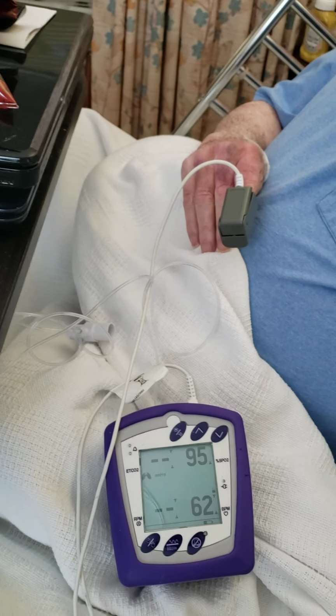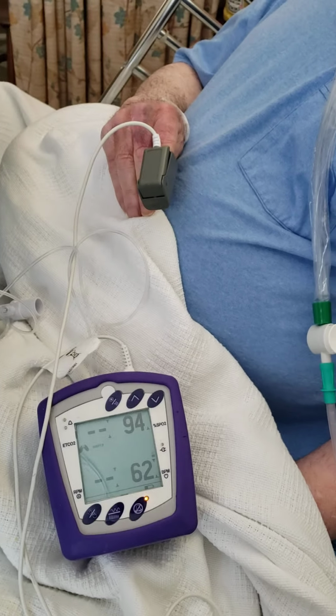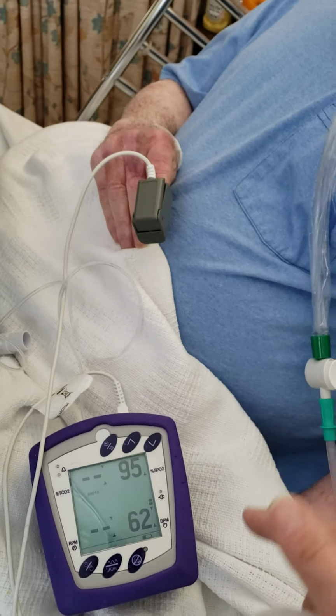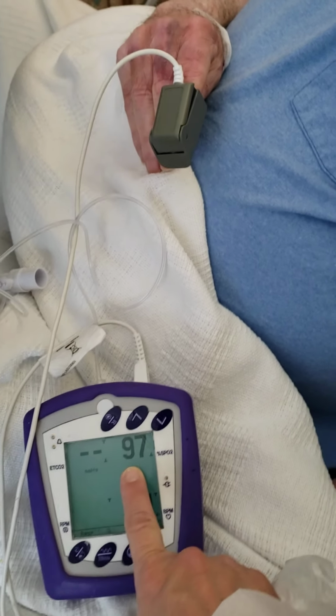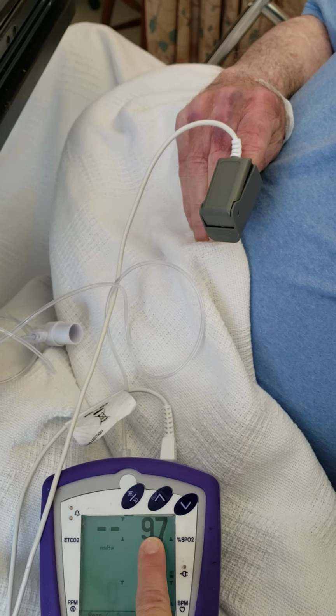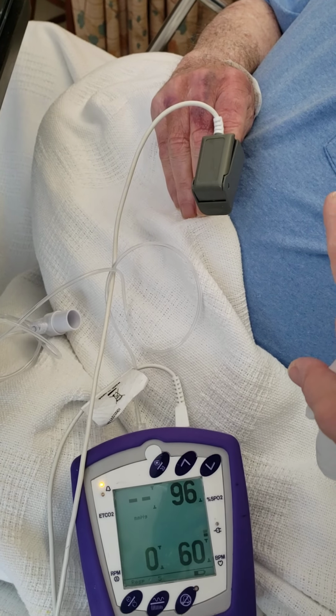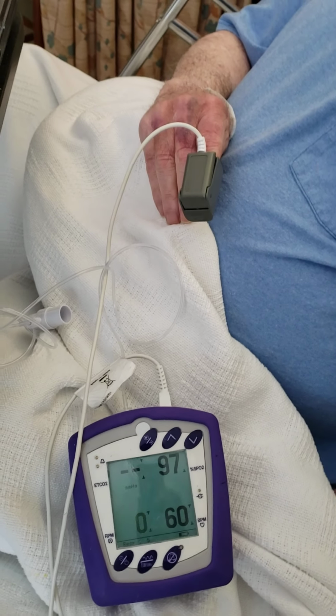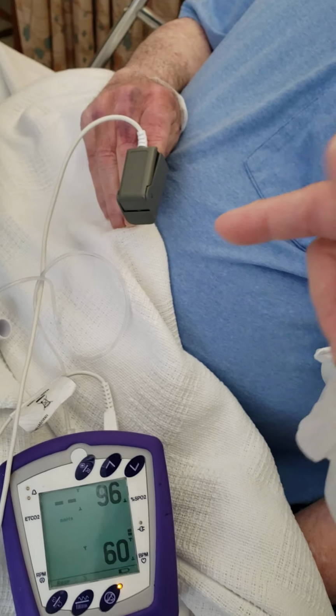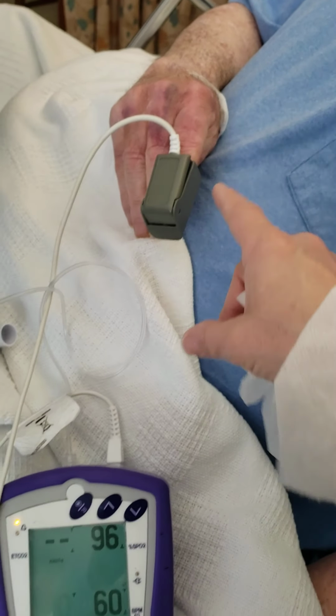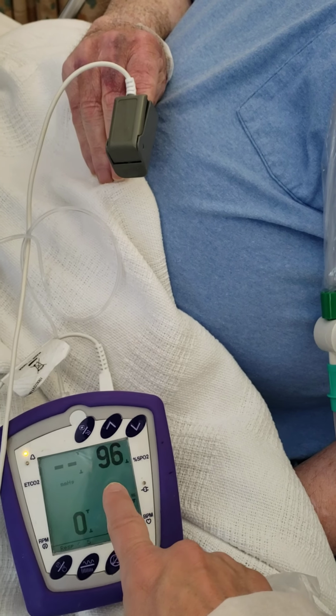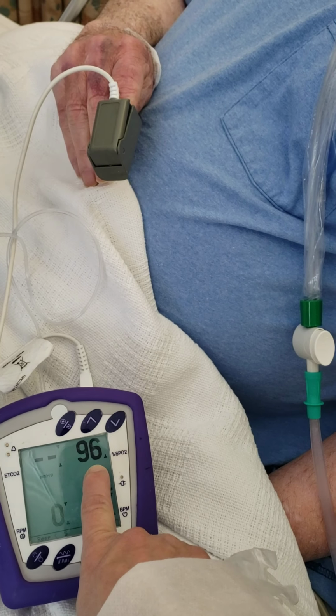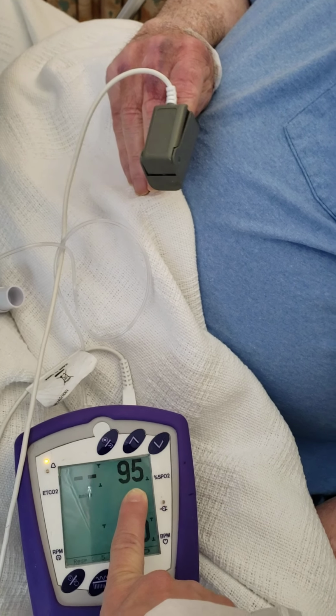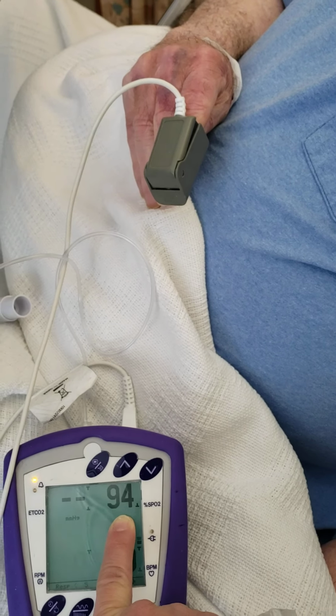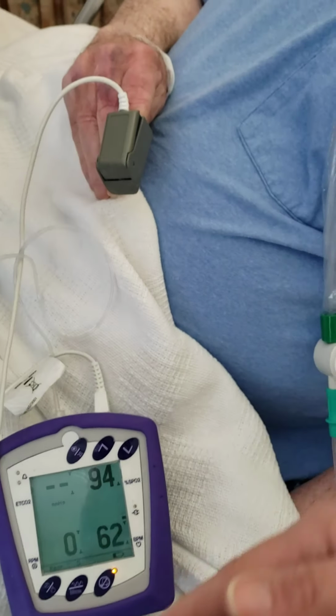So if there is oxygen attached to the red blood cell, that iron bond would reflect the light coming through his finger. The measurement tool in here is deducting from 100%. If all of the light bounces back off of him, that means all of his oxygen is on the hemoglobin. If it's not, and it's going through, it deducts the amount that comes through and gives us a reduced number. He's currently set at 95, because that means 95% of the light is being reflected off the oxygen and coming back to the sensor.